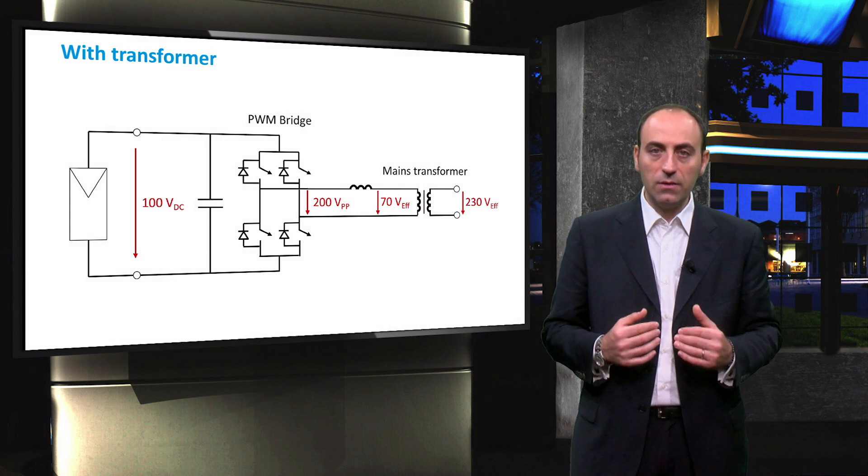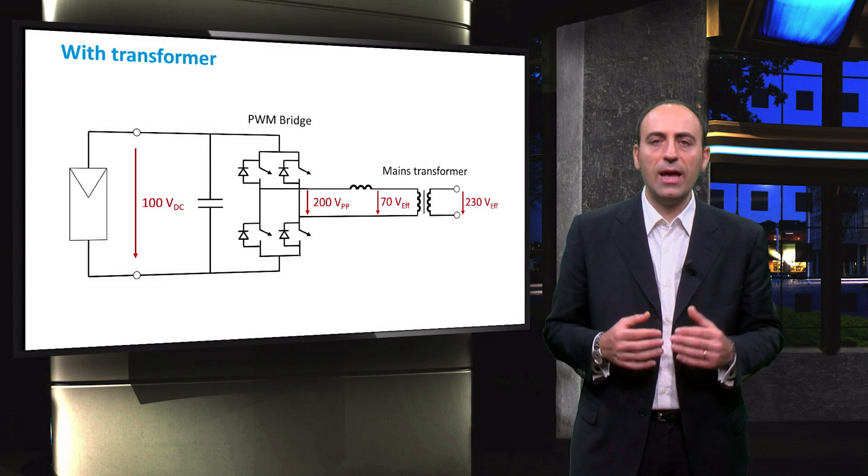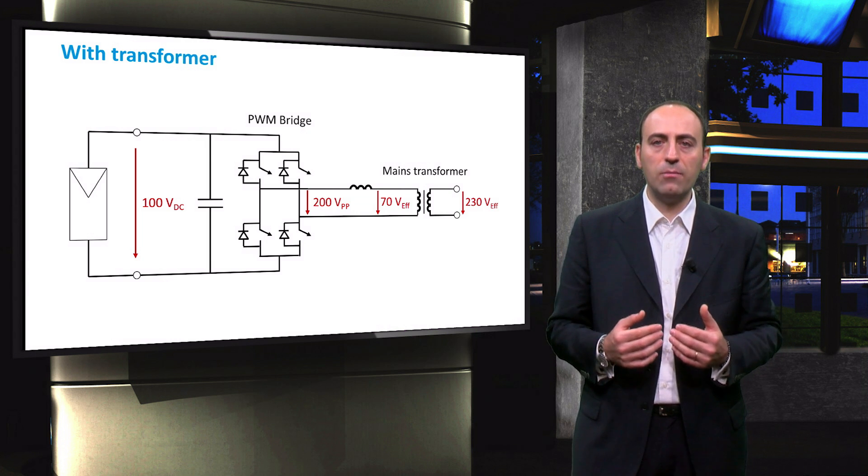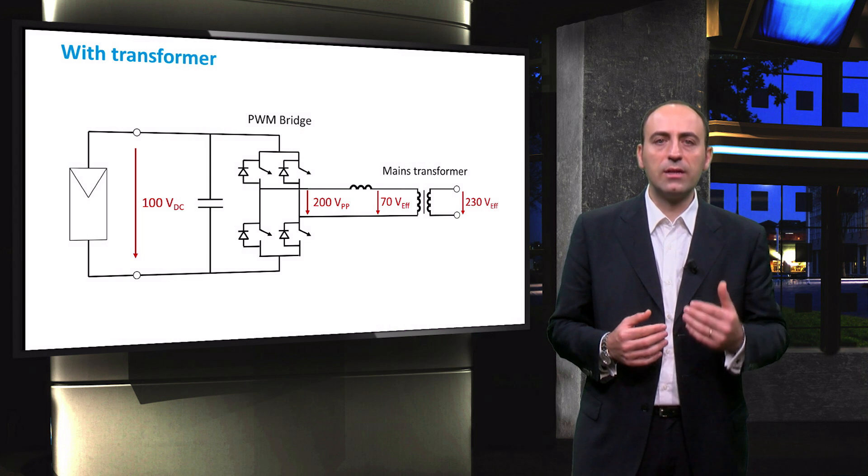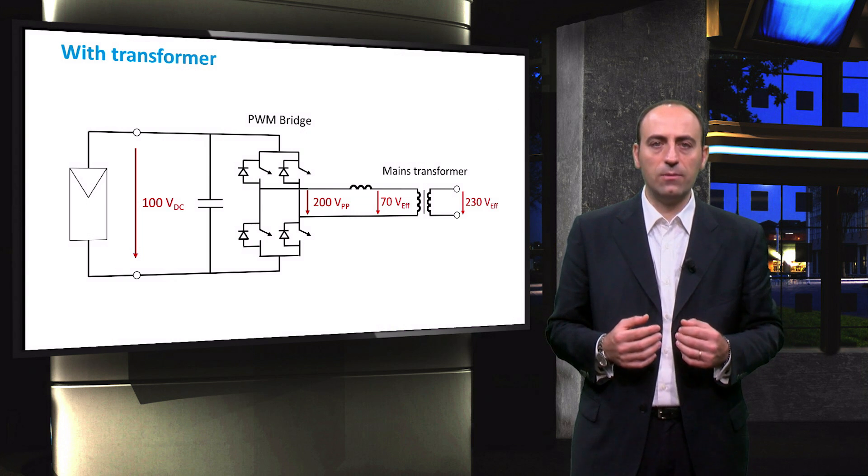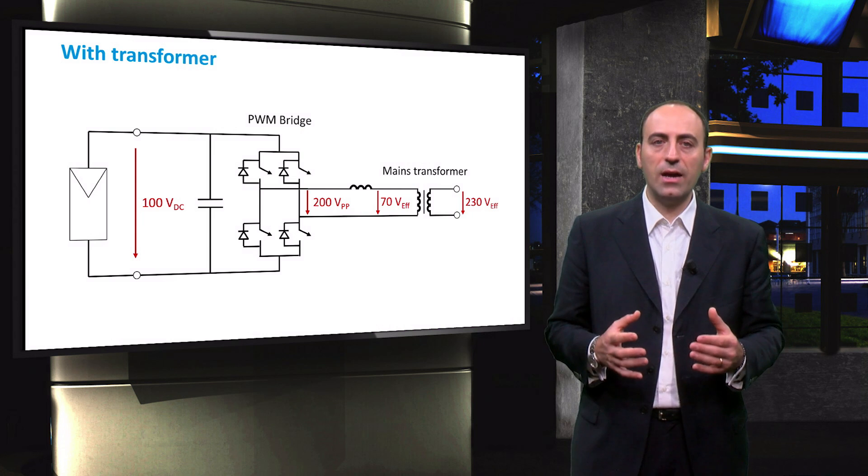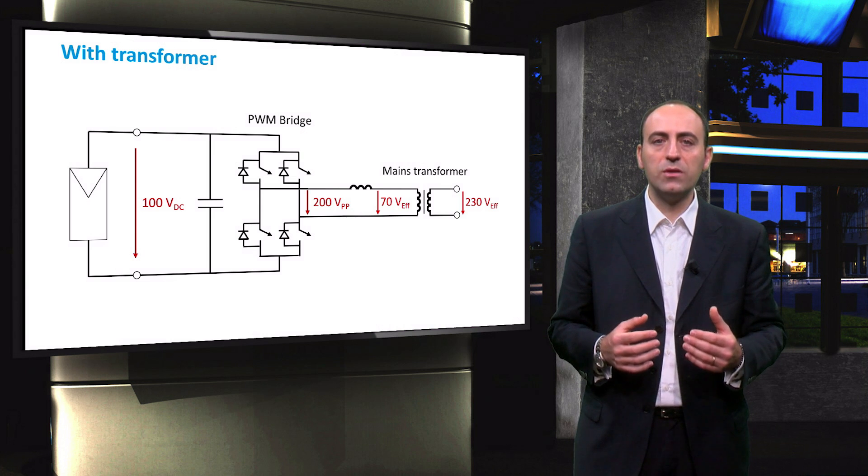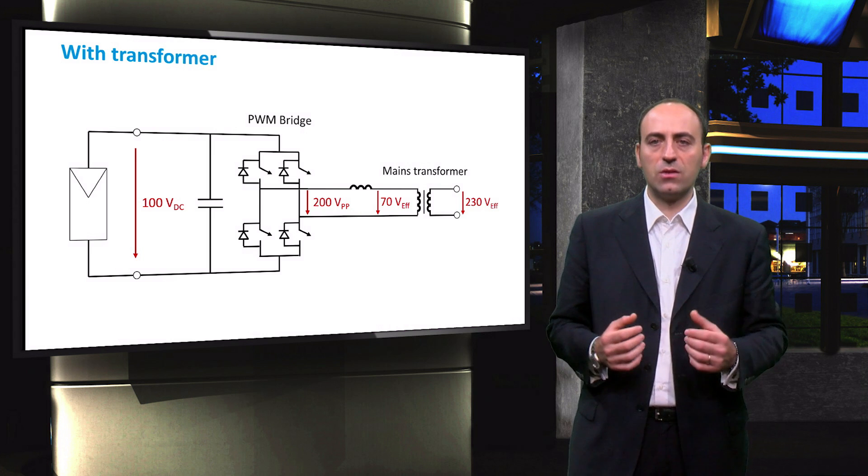As an alternative to the 50Hz transformer, a high-frequency transformer can be used to permit galvanic isolation of the DC and the AC side. Since the frequency is higher, the transformer can also be smaller by some factors and therefore cheaper than the mains transformer.